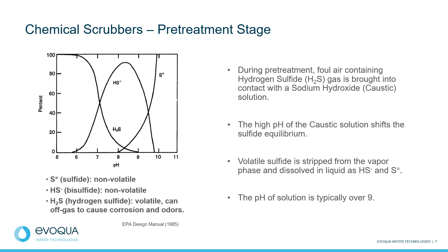Once that pre-treatment has occurred, these dissolved sulfide species are then allowed to mix with bleach solution in the odor removal stages. That bleach solution will then oxidize the sulfides based on the following reactions. If the pH is between 7 and 9.5, those sulfides are oxidized into elemental sulfur. If the pH is higher than 9.5, the sulfides will instead be oxidized to sulfate.